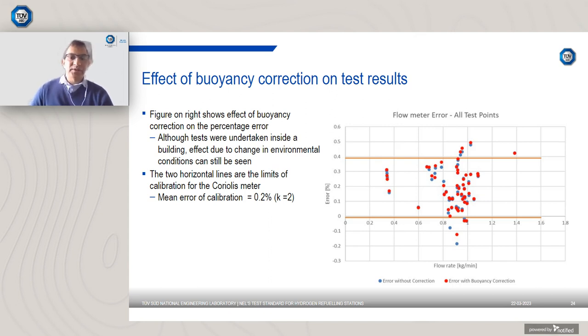The data that's shown on this graph is for all 55 tests, and basically the data points in blue are when you do not apply any buoyancy correction. The data points in red are after you have applied buoyancy correction. And what you can essentially see is that even though the tests were carried out inside a building, applying buoyancy correction has a small impact on decreasing the error. The two horizontal lines that you can see here are essentially the limits of calibration of the Coriolis flow meter that was used.